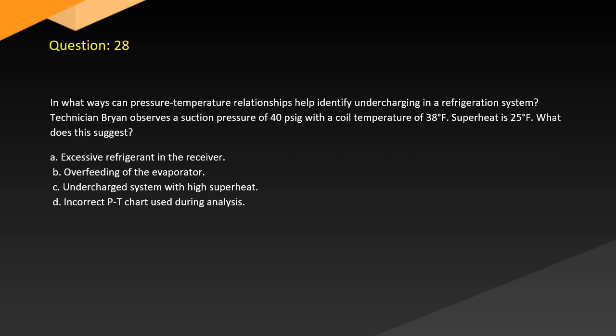Question 28. In what ways can pressure-temperature relationships help identify undercharging in a refrigeration system? Technician Brian observes a suction pressure of 40 psig with a coil temperature of 38 degrees. Superheat is 25 degrees. What does this suggest? A. Excessive refrigerant in the receiver. B. Overfeeding of the evaporator. C. Undercharged system with high superheat. D. Incorrect PT chart used during analysis.